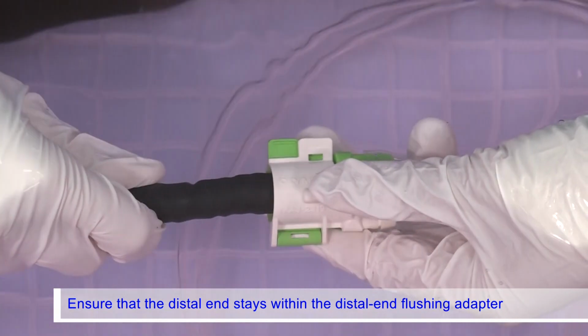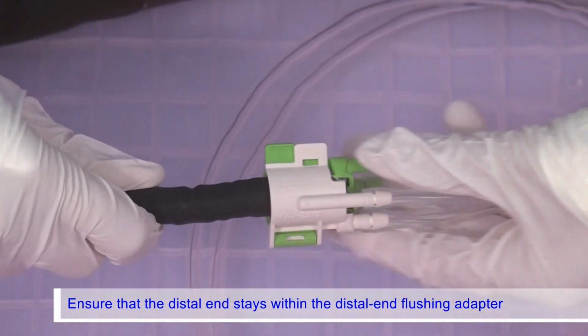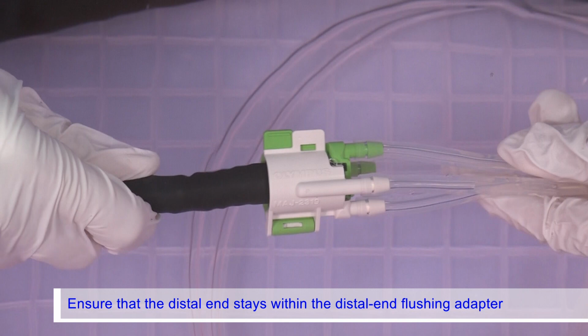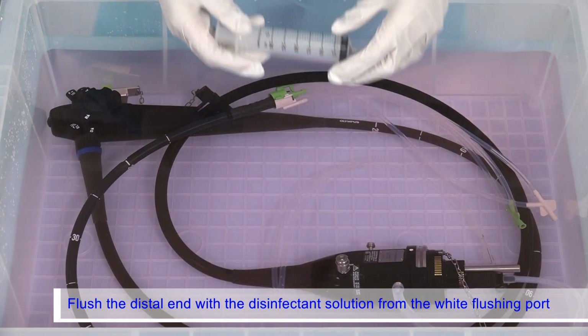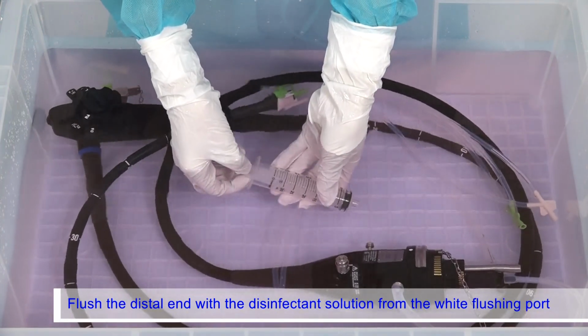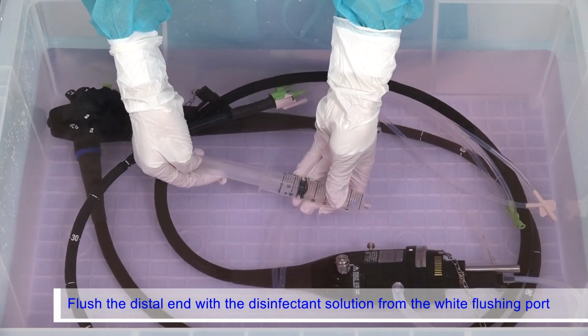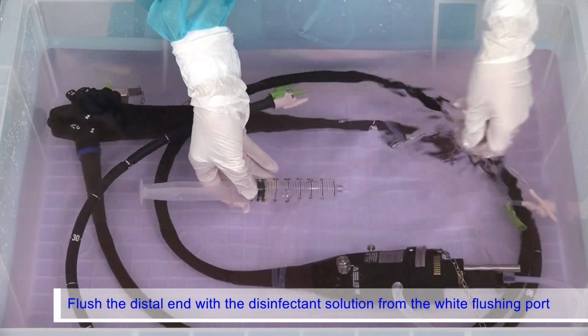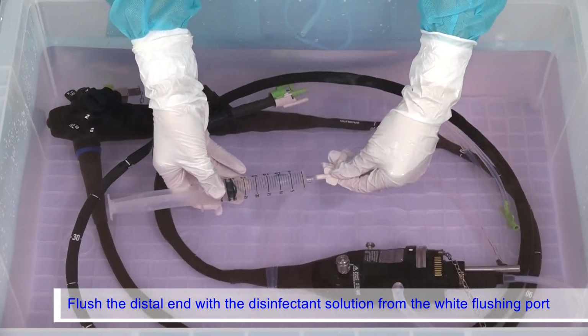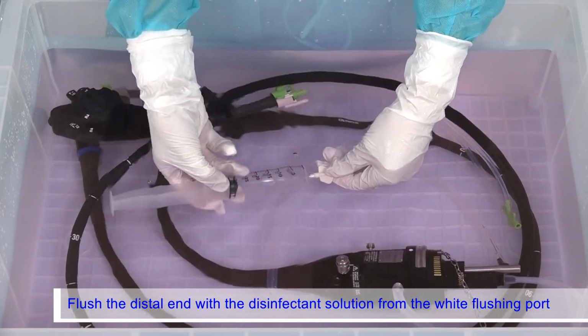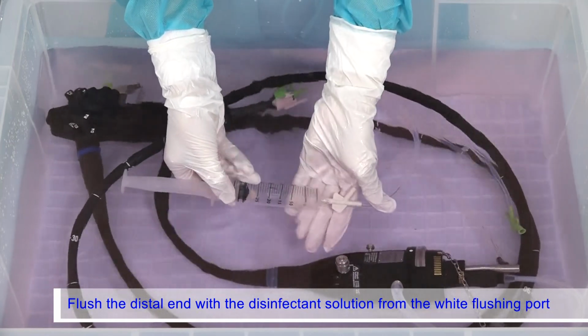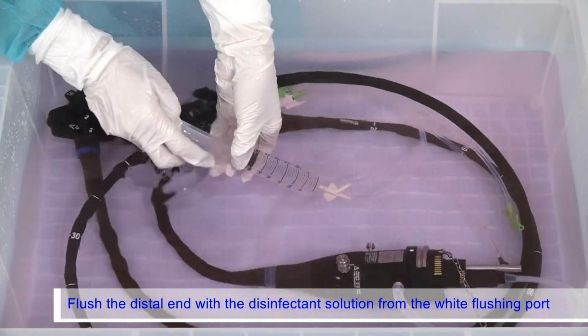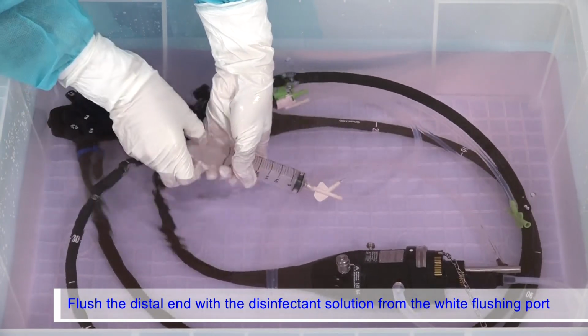While immersing the endoscope and the distal end flushing adapter completely in the disinfectant solution, hold the distal end flushing adapter and gently pull the endoscope to ensure that the distal end stays within the adapter and does not come out. While immersing a clean 30 milliliter syringe completely in the disinfectant solution, slowly fill it with the disinfectant solution, attach it to the white flushing port of the distal end flushing adapter, and forcefully flush the distal end with 30 milliliters of the disinfectant solution.